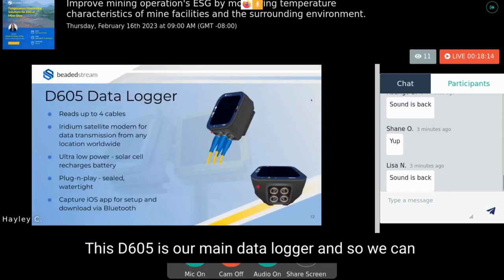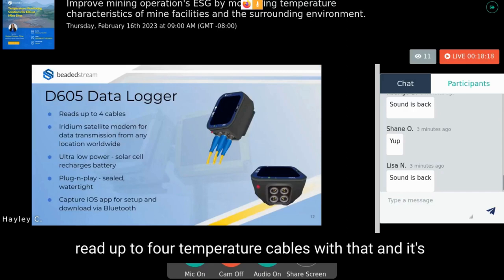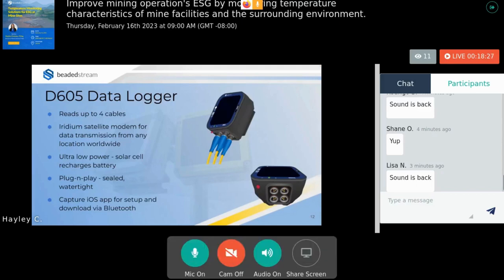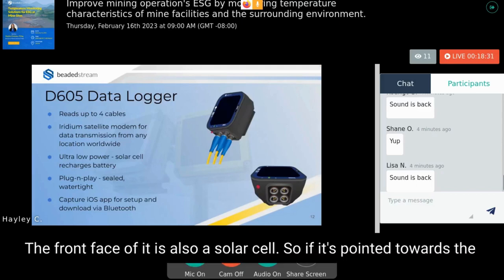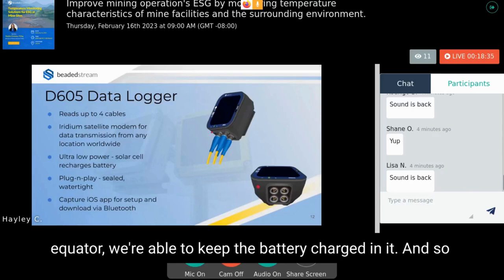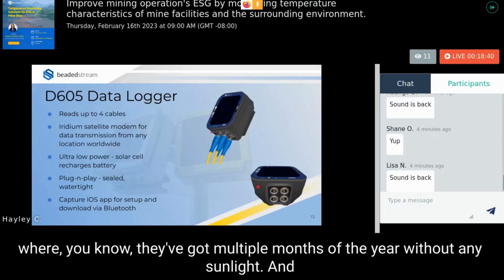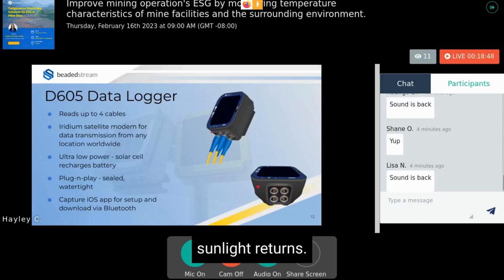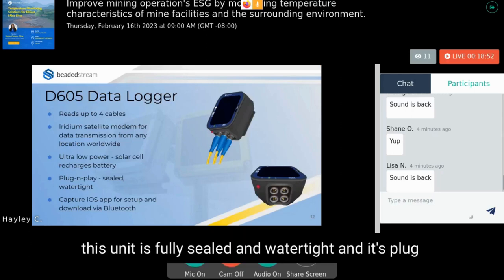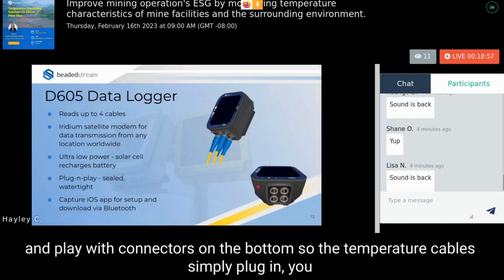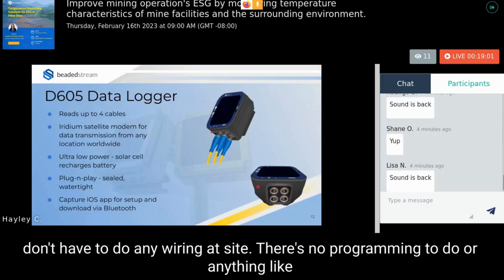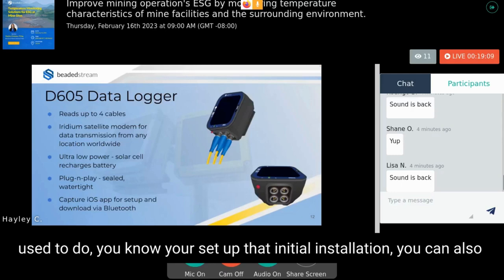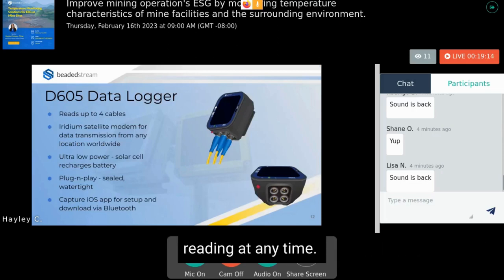The D605 is our main data logger, which can read up to four temperature cables. It has an embedded Iridium satellite modem for data transmission from anywhere in the world, and the front face is also a solar cell — so when pointed toward the equator, it keeps the battery charged. It works through darker months in far northern locations and starts charging again when sunlight returns. The unit is fully sealed and watertight, plug-and-play with connectors on the bottom — no wiring or programming required at the site. We also have a Capture app for iOS for setup, local data download, and spot readings.